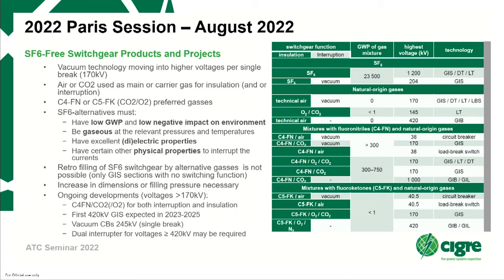The two most preferable SF6 alternative gases include C4 fluoronitrile or C5 fluoroketone mixed with CO2 or O2. The new alternative gases must ideally have zero or low global warming potential and low negative impact on the environment, be gases at the relevant pressure and temperature, and of course have excellent dielectric properties and certain other physical parameters to interrupt the currents.